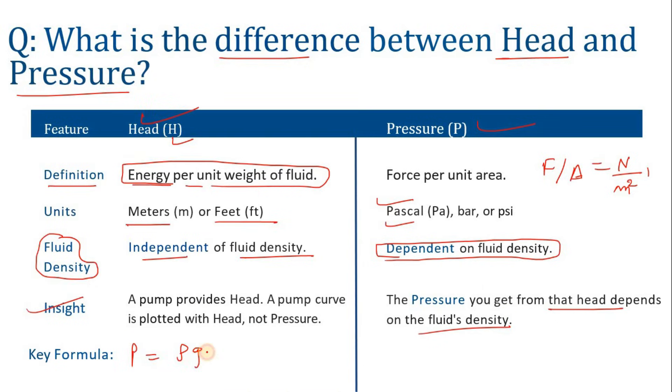Now this head is independent of the density. So let's suppose if you have 30 meter head, whether you use oil or any other fluid, that pump can lift the fluid 30 meters. But when we calculate the pressure, density will come into the picture. Density can vary with respect to fluid. That's why it is said that pressure is dependent on the fluid density but head is not.